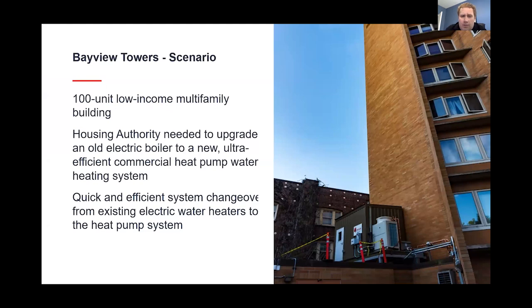So this is an example of a project called the Bayview Towers in Seattle, Washington, where we converted 100-unit low-income multifamily housing from an old electric boiler to a new ultra efficient commercial hot water heat pump heating system. They chose to make a little skid package and a housing off site here. That is not what you have to do on all projects, but this is what they chose due to the space constraints they had.